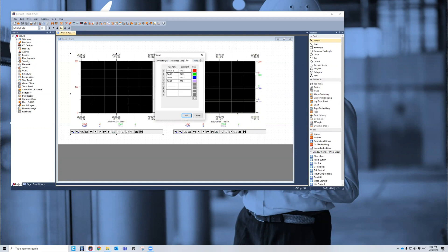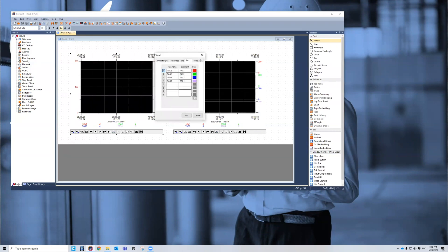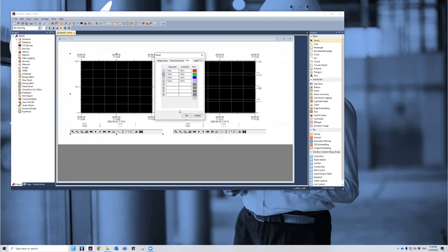And then these are the tags that I will be dealing with. Red, green, blue, light purple, tag one through four. Make sure that you name a min and a max. If you don't, the tag will not graph on the trend. And I did that for each of these tags, zero to 300, because we're randomizing between zero and 300. You can have up to a max of 16 tags per trend.